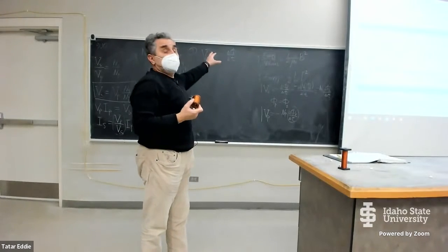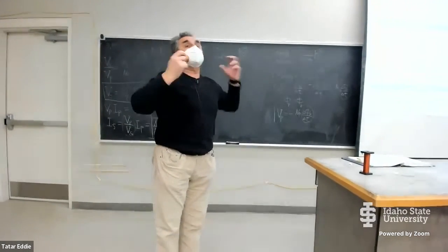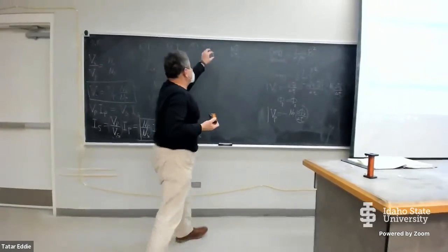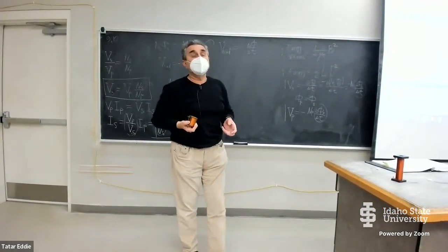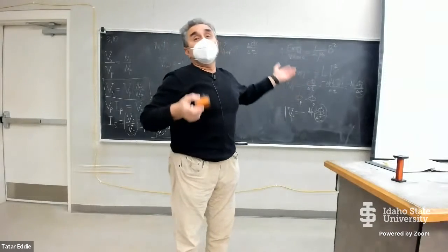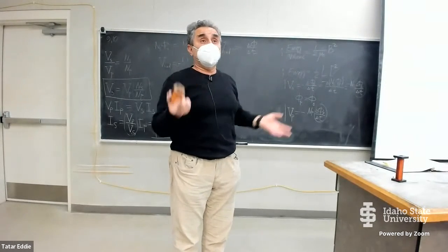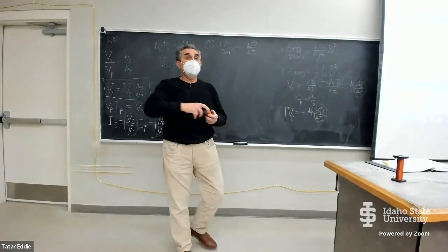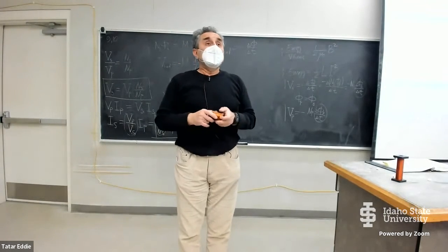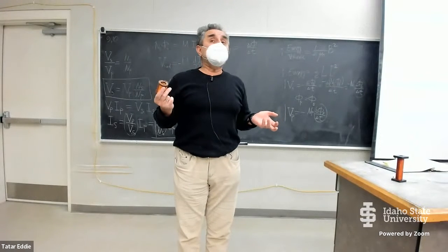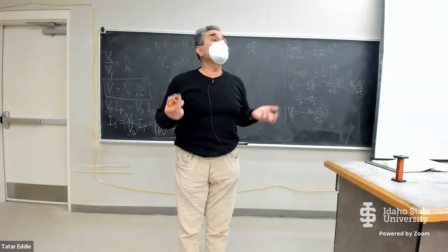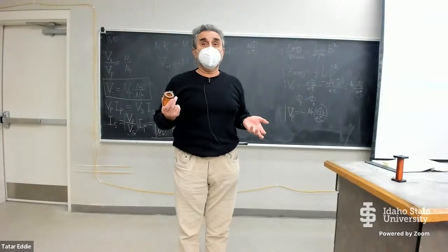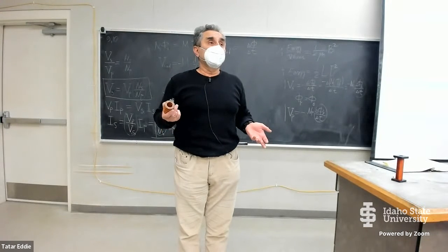The magnetic field goes from 3 Tesla to 0. Therefore, the magnetic flux through the patient goes from whatever value it is to 0. And therefore, you have induced voltage in the patient's body. That induced voltage is going to drive current, and that current may fry the patient, may just kill him.